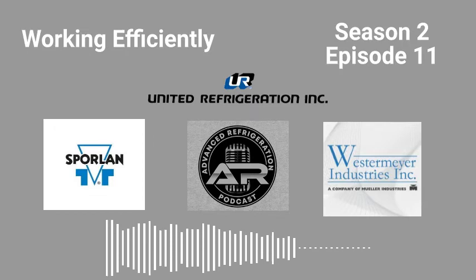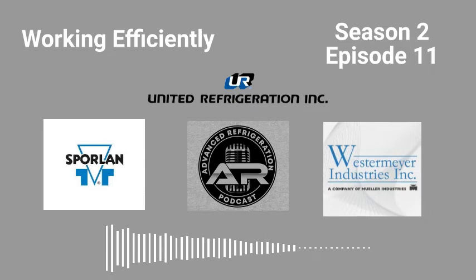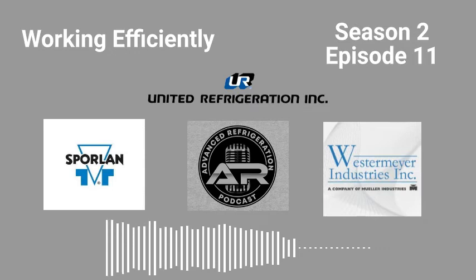I'm using a 5/8 tap. Remember, your flow is also affected by other things. If you have a service valve fitting with a Schrader in there, pull the Schrader. One with threads in it actually pulls slower than one without the fittings in there for a Schrader. So anything you can do to reduce that vacuum time is extremely helpful.